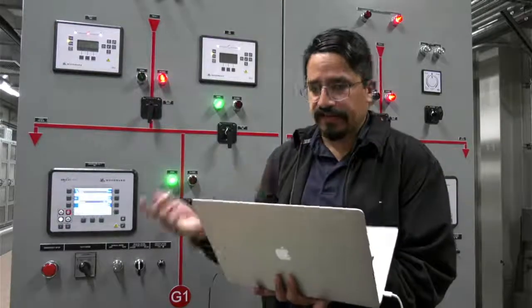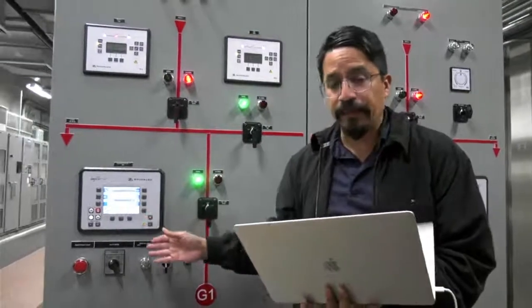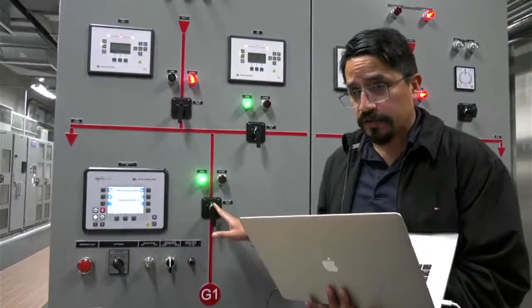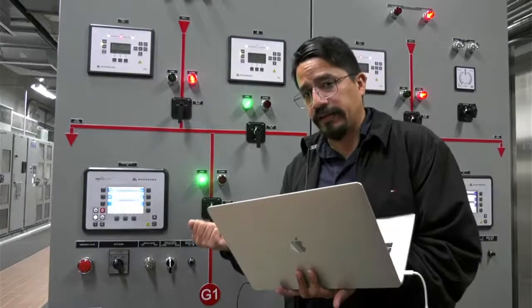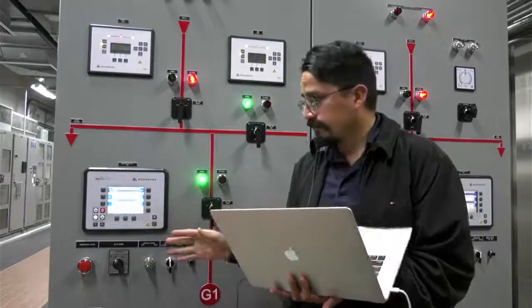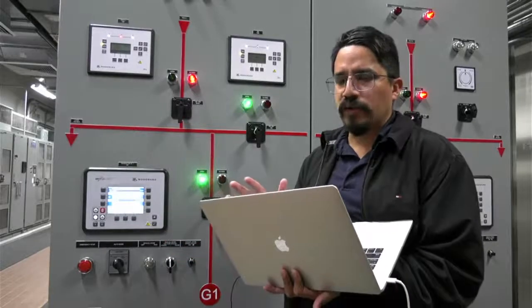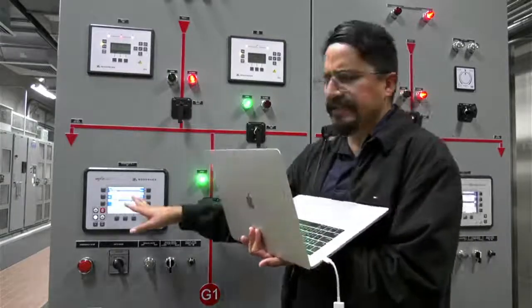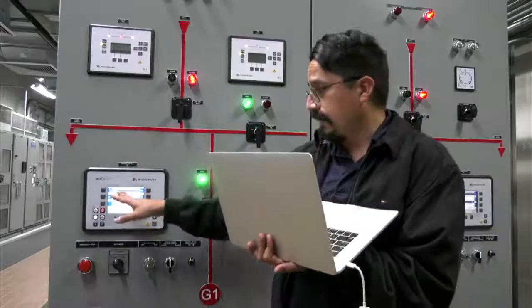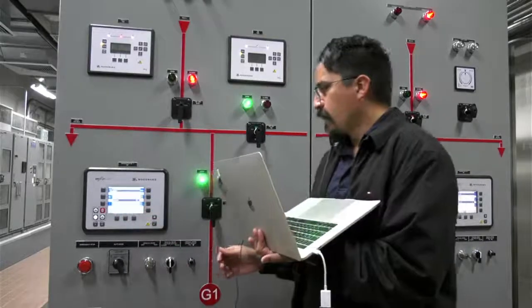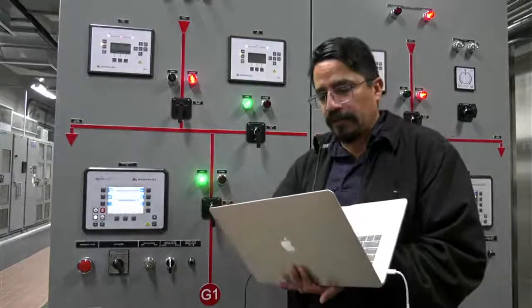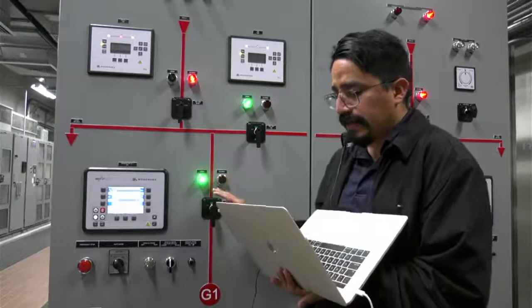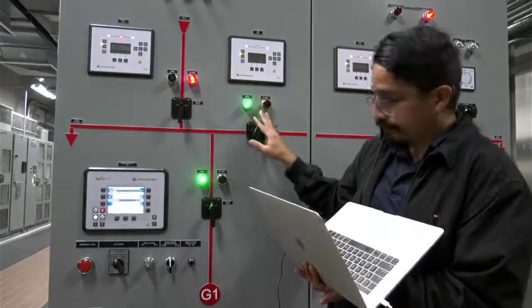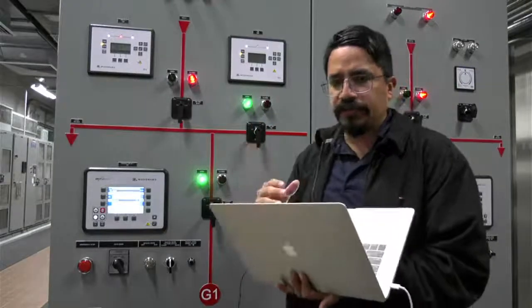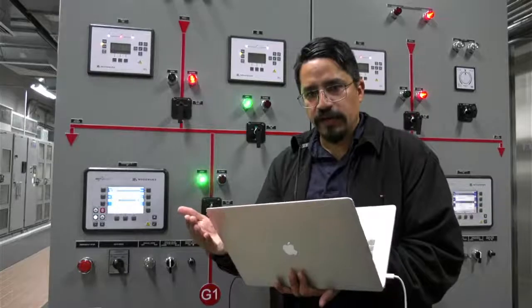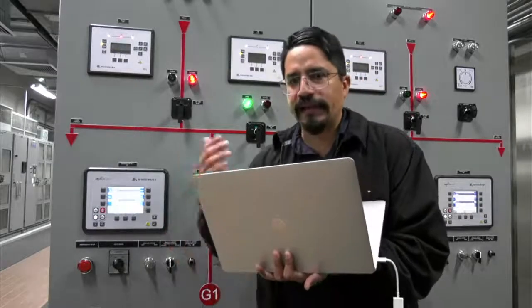The same happens with the circuit breaker. If the generator is running in manual, the circuit breaker is not going to close. So we need to come here and close the circuit breaker after the generator is stable. Usually that's around 20 seconds, and the DCGen, if it's available, is going to help you, saying that the generator is stable or not. In auto, so in automatic mode, all the engines, GCB, MCB, tiebreakers, they are operated by the automatic mode, which means it's not waiting for the operator to do any action.